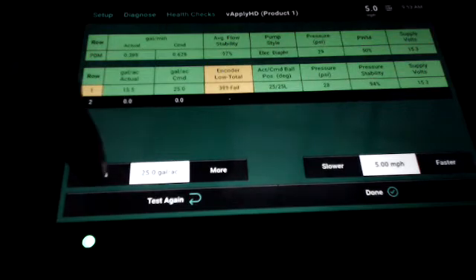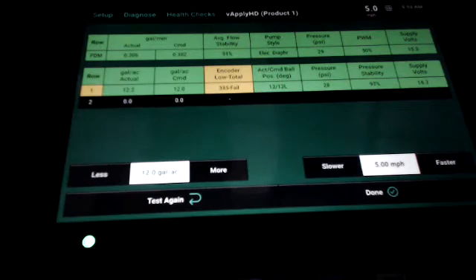So if we would slow down to where the ball position goes less than 25, you'll hit your target rate. And we'll see that here, 12 gallon target. We're hitting our rate, and the ball position is only at 12 or 13. So that's how that works.